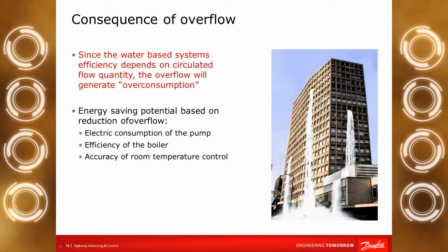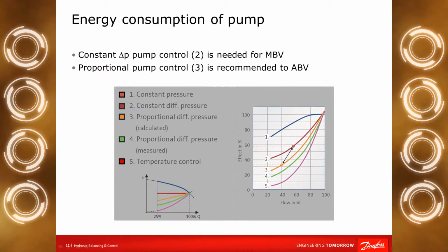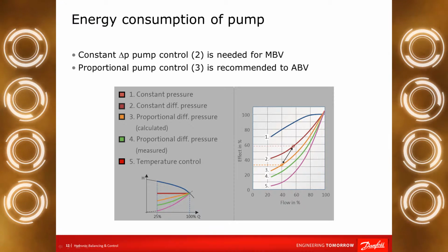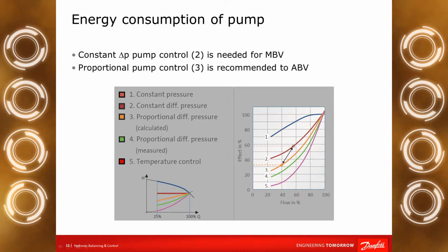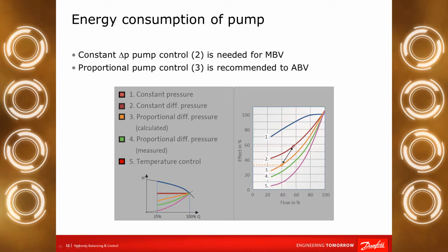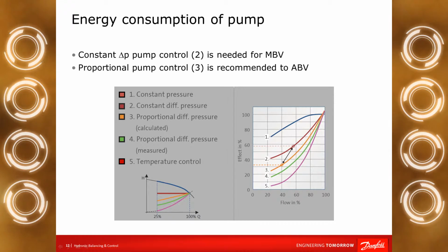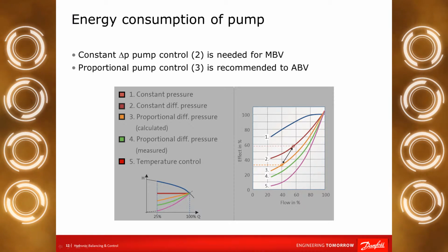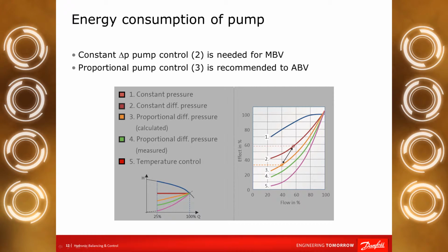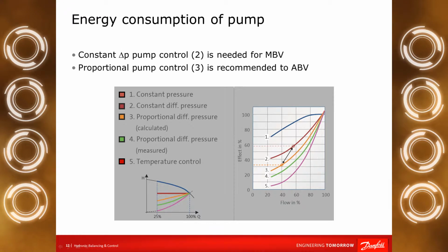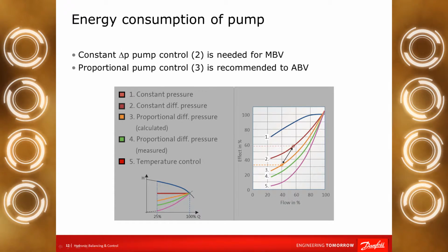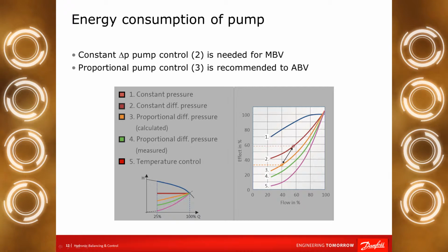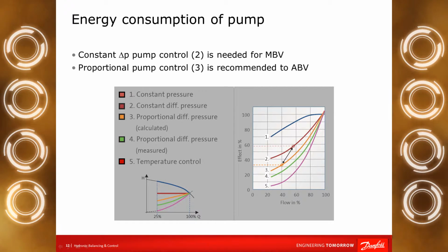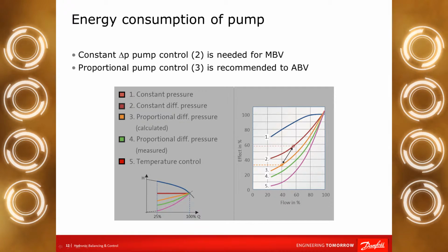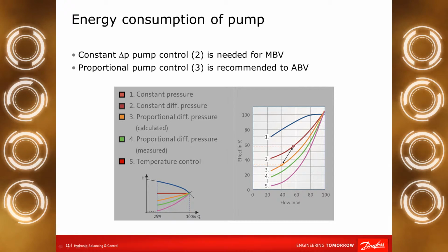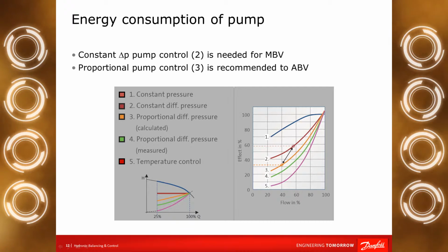Let's see them one by one. The first one is the energy saving on the pump. You can see on the picture the comparison of the energy consumption in case of usage of constant delta P control on the pump, and with orange, the energy consumption of the proportional pump control. If we have a manual balance system, we must use constant delta P control on the pump, otherwise there could be some suffering terminal units because of underflow. In case of automatic balancing valve, we can use proportional control, which consumes much less energy.